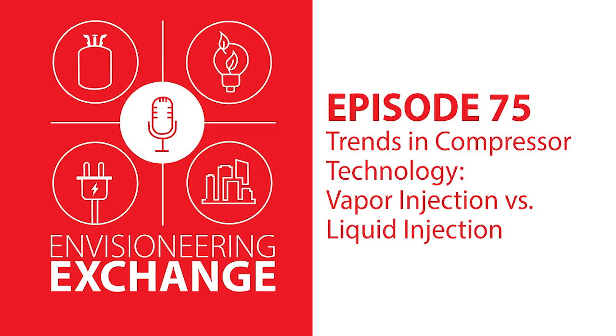Without it, you can have a reversible unit and it can run in moderately cold climate zones. Maybe from the north of the US down south, heat pumps are okay to run on a standard compressor. But as you go north into some of the colder ASHRAE climate zones, you really can't use a heat pump without some other source of backup heat, with electric heat or hydronic or gas heat. You have to have some other heat to kick on when the heat pump's no longer able to meet the demand. But when you add vapor injection, our compressor map is so wide that we can cover almost the entire United States in most cases, and in some cases even into Canada, without needing a secondary heat source. So that's really the benefit. And when we do that, we're not burning any fossil fuels, energy efficiency is increased, and the decarbonization goals are kept intact. That's the main draw.